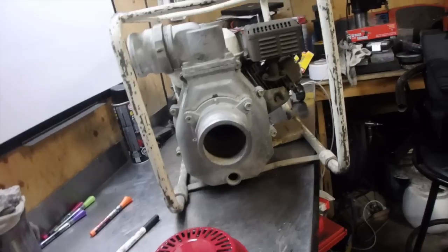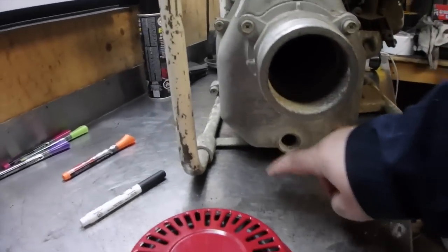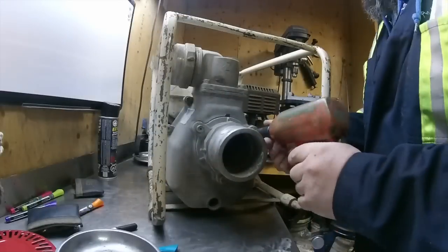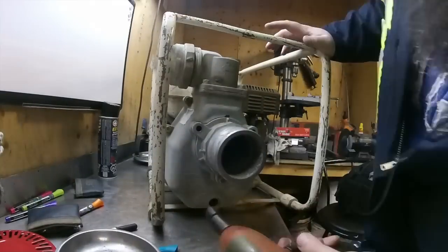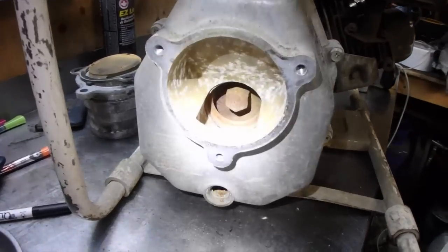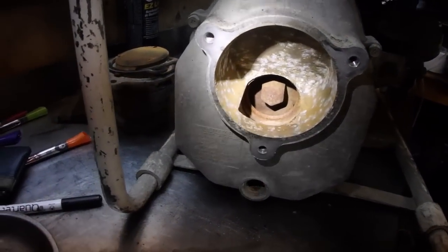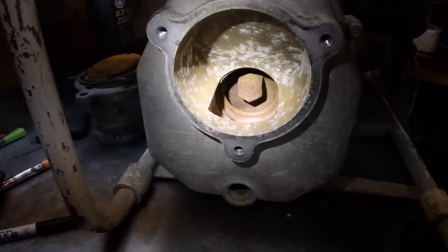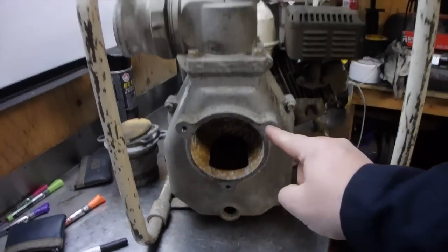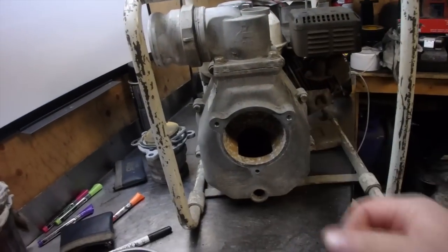I'm just going to take everything apart for inspection because I know we don't really need to remove this, but I'm going to remove it anyway. Then we'll pop this top piece off and remove the outer shell. You can see right there how the water drops down below and hits the impeller and swings it around. I can tell by looking at the impeller that the direction of rotation is going to be up and out. So let's remove this top piece and then remove this outside case.